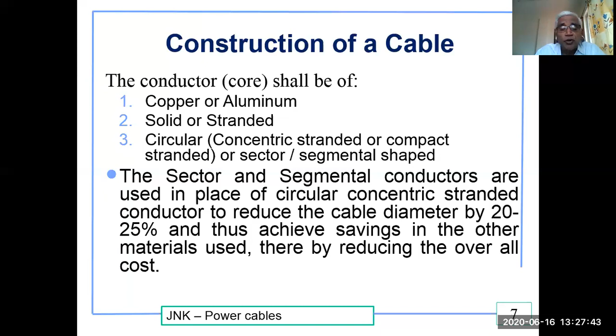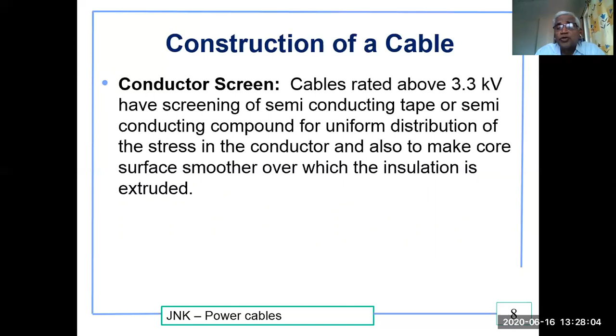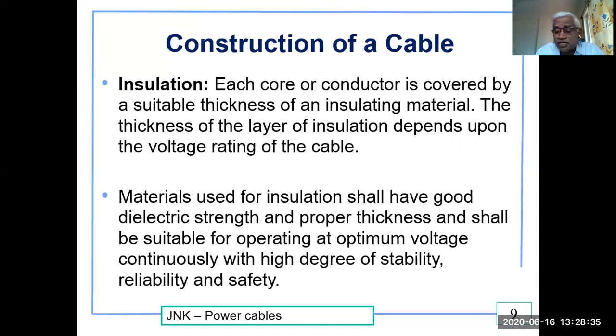Conductor screen. Cables rated above 3.3 kV have a screening of semiconducting tape or semiconducting compound for uniform distribution of stresses in the conductor and also to make the surface smoother over which the insulation is extruded. Insulation. Each core or conductor is covered by a suitable thickness of an insulation material. The thickness of the layer of the insulation depends upon the voltage rating of the cable. Materials used for insulation shall have a good dielectric strength, proper thickness, and shall be suitable for operating at an optimum voltage continuously with a high degree of stability, reliability, and safety.